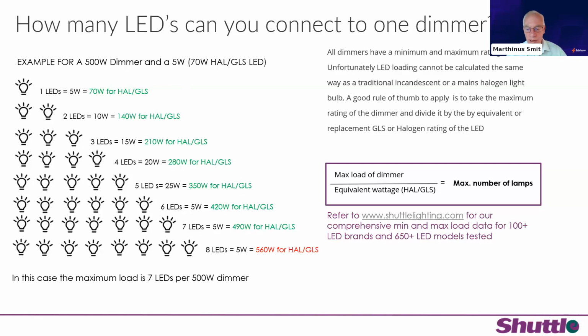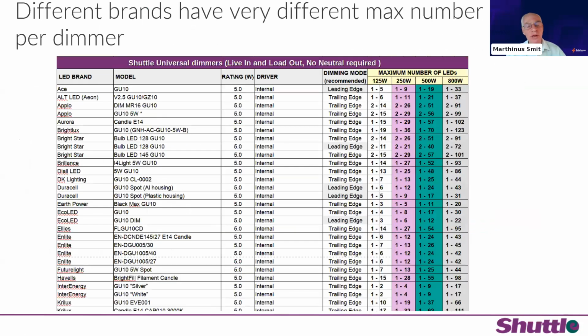Now, this is the official recommendation if you have no idea what your dimmer or your lamp behavior is. Because this is very limiting, a lot of dimmer manufacturers, and even lamp manufacturers, supply compatibility charts. Interestingly, this is our own in-house measured chart. This is a small example of more than 700 lamps that we have tested. This is a snapshot of some of the 5-watt LEDs, and you can see some of them are recommended for leading edge, some of them for trailing edge. And you can see that the maximum number of lamps differs significantly according to model and according to brand. Now, this is not an indication of lamp quality. It's purely a result of how the driver is designed.